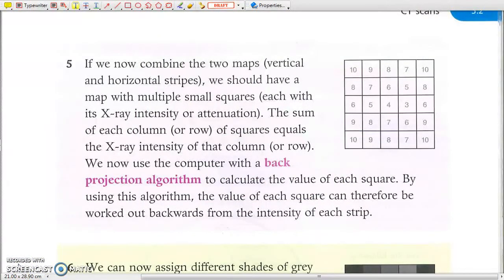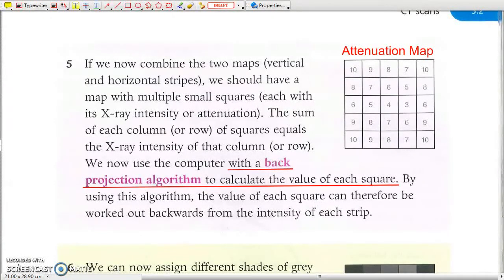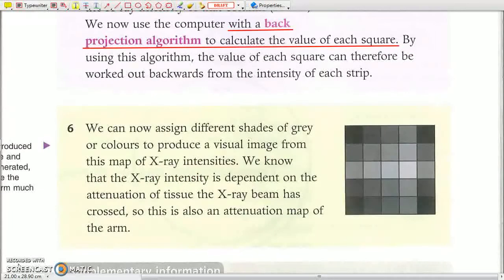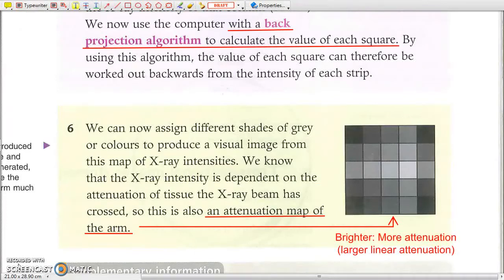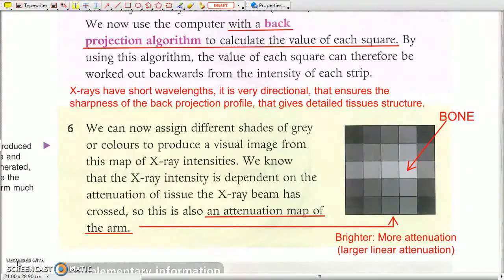The two attenuation profiles are combined into an attenuation map of the tissue structure, which is a numerical representation of the tissue structure. A smaller number in the attenuation profile, which is actually the transmitted intensity, corresponds to the tissue of higher attenuation. And in this way the bone can be located. And as X-rays are very directional, it ensures the sharpness of the back projection profile, and that may give more details of the tissue structure.